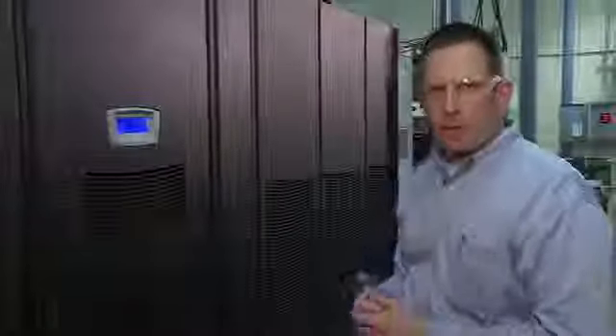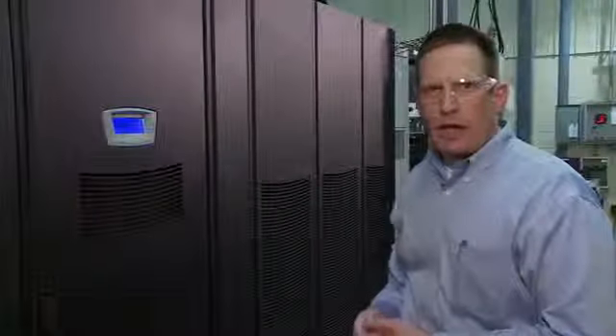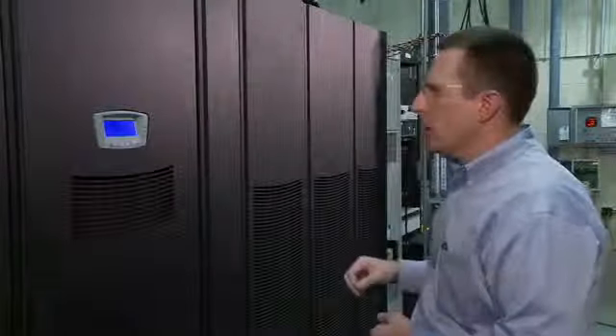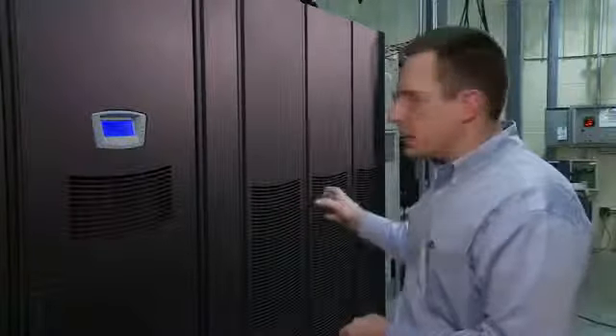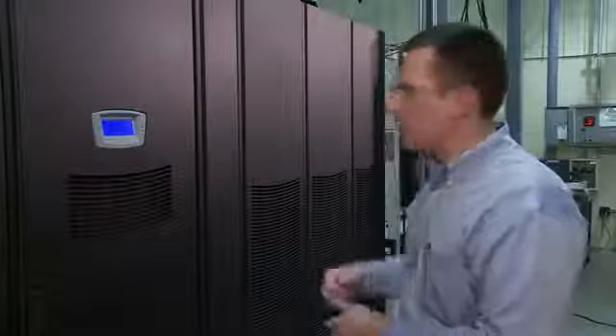Now the system is running online in double conversion mode. It's fully loaded with a resistive load at 1000 kilowatts. The load bank is located outside with a control panel on the back wall. The system is also fully metered for input and output voltage and current, as well as the fault current that we're going to see on the battery. These images will be captured on an oscilloscope that's off to the side of the system.